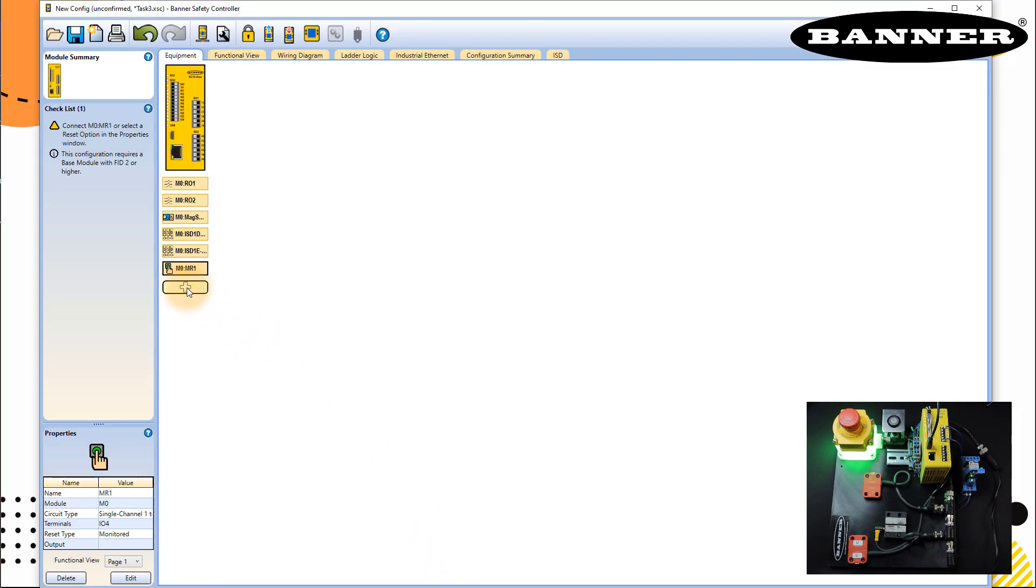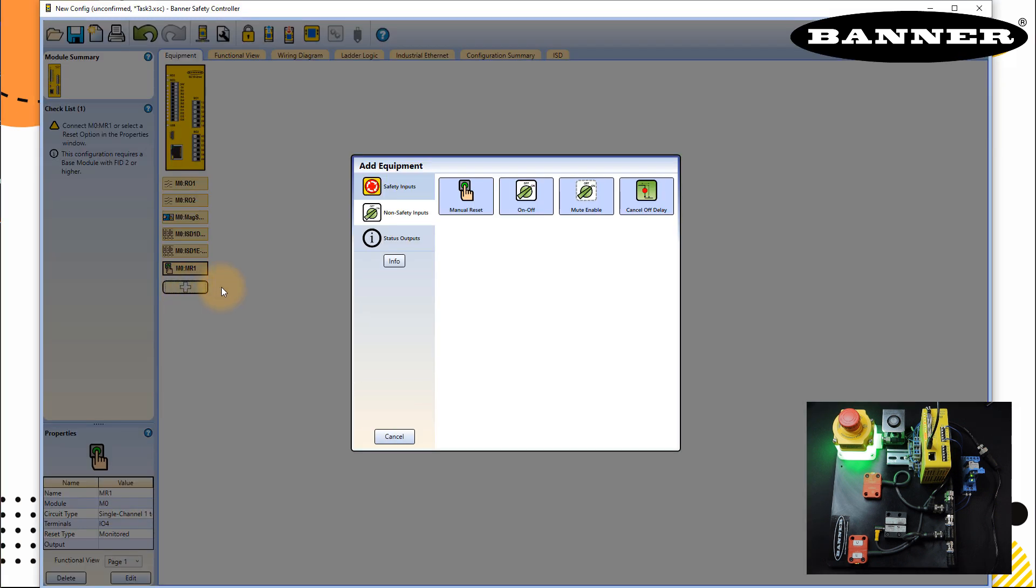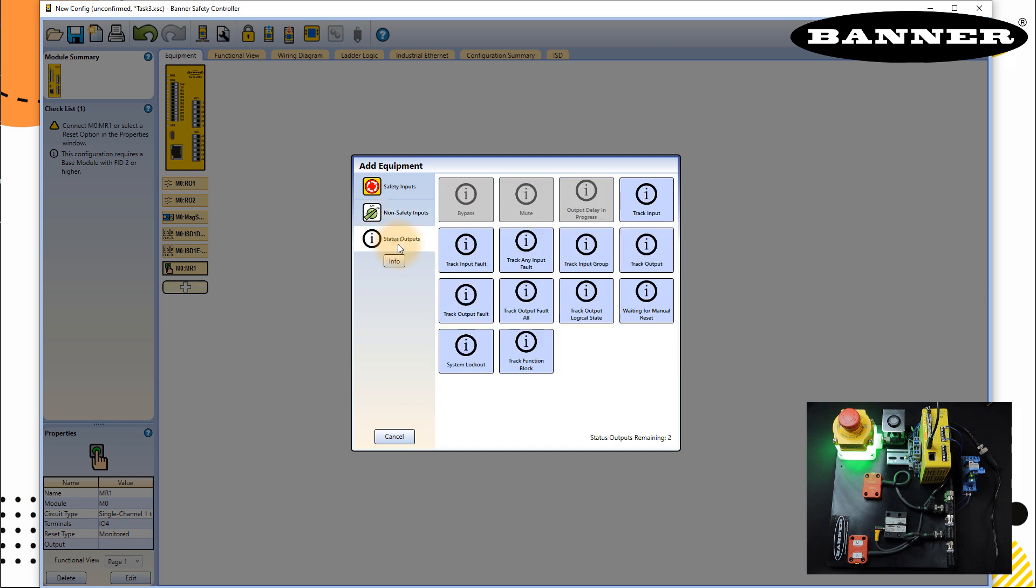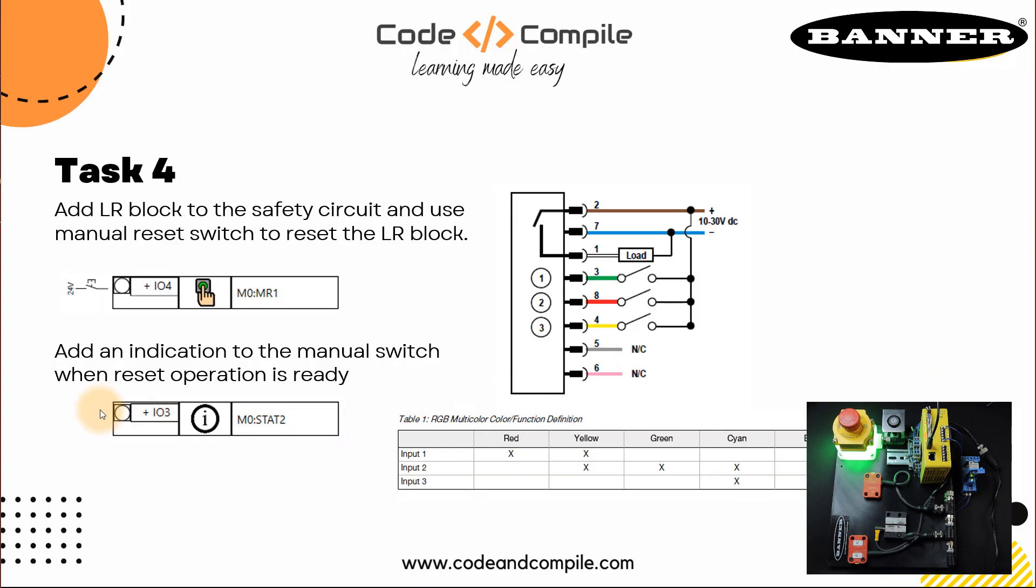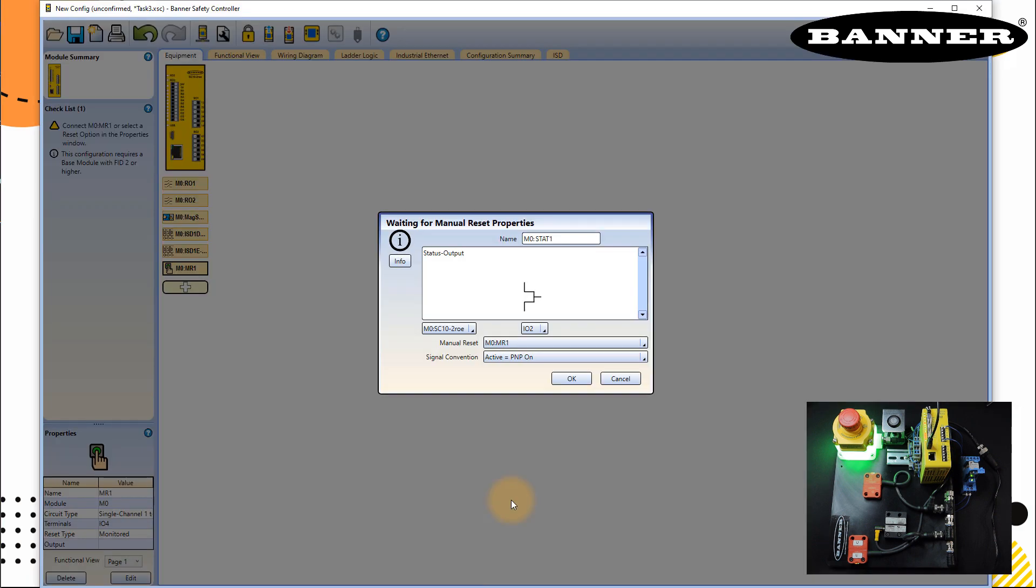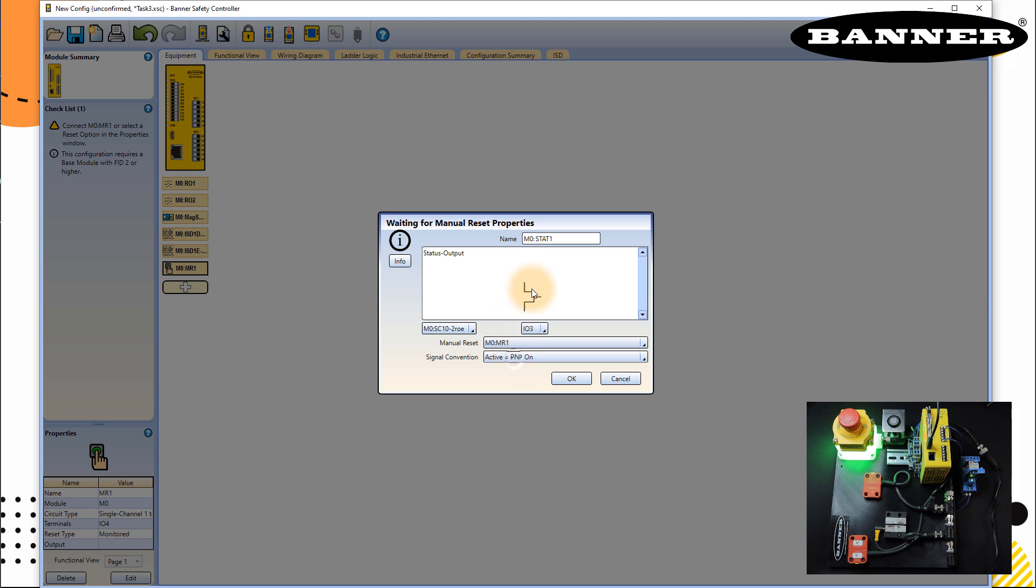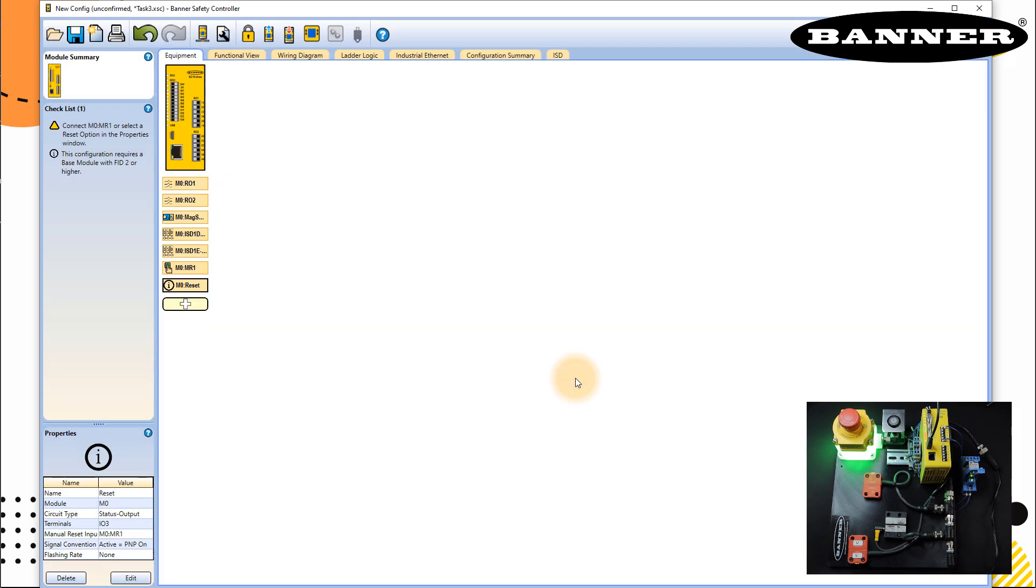And now we take the status output. Remember that status output, we will select waiting for manual reset. So we have already predefined input for that, which makes it super easy. Click on this one. And you can see this is in status output and this is connected to IO3. So select your input IO3 and select which manual reset button, which is MR1, which we defined in the last step. So this is the status, and this is saying ready to reset. So I will just write here reset and click okay.